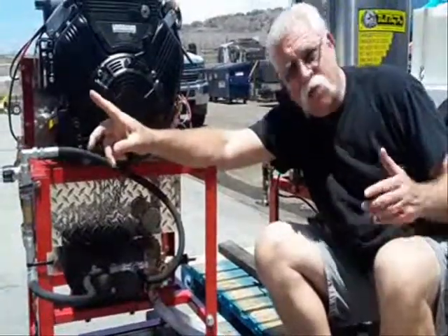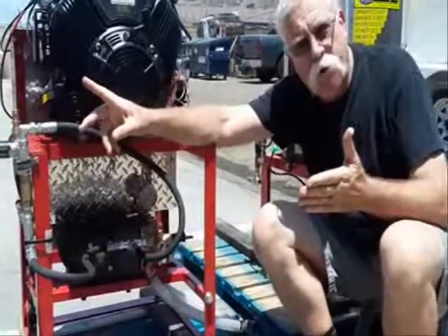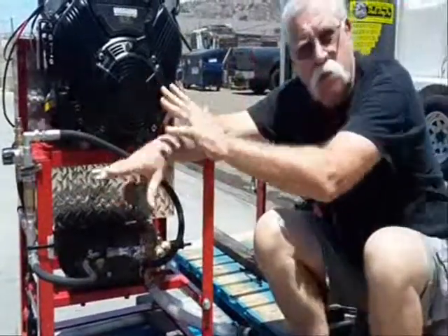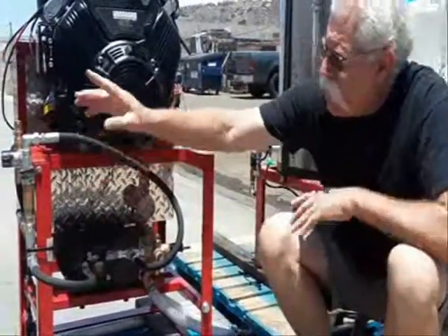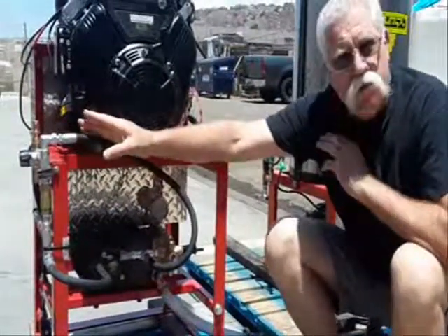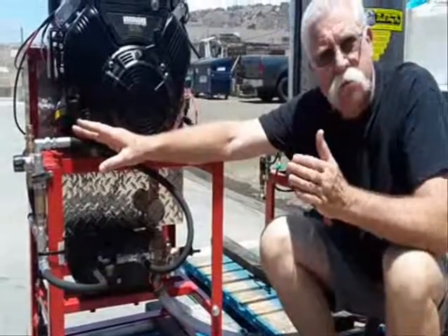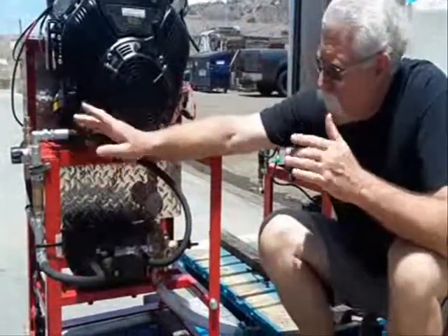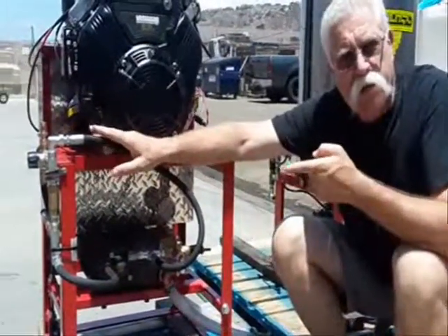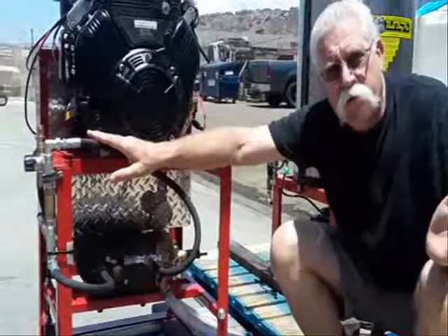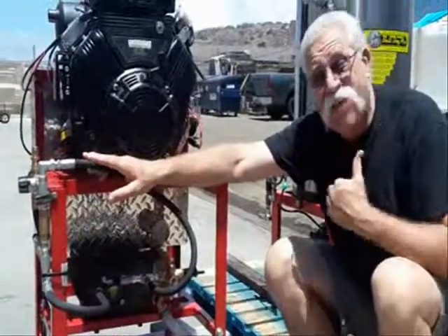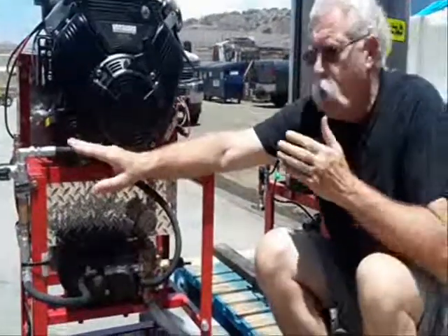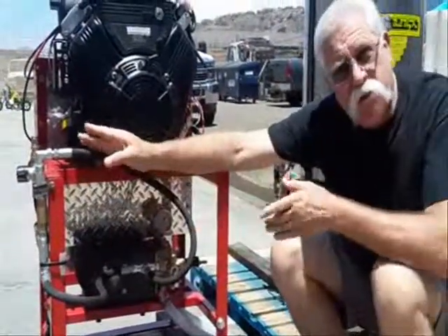And again, it should go into a no-load bypass when you open and close the gun, even at the lower pressure range. Okay, that regulator you can adjust from 1,000 to 2,000 psi, no problem. In fact, I think we put this lower pressure regulator on here so you can go down to 500 psi when you want to have steam. Okay. So you've got an adjustable range that you can mess with on this unloader.